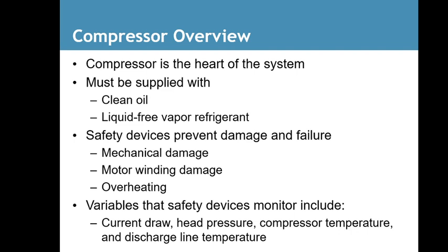Compressor overview: the compressor is the heart of the system, as discussed in Chapter 18. The compressor must be supplied with clean oil and liquid-free vapor refrigerant. Safety devices prevent damage and failure — including mechanical damage, motor winding damage, and overheating. Variables that safety devices monitor include current draw, head pressure, compressor temperature, and discharge line temperature.